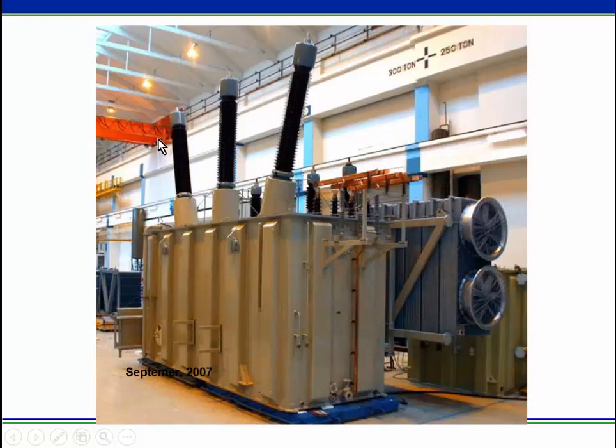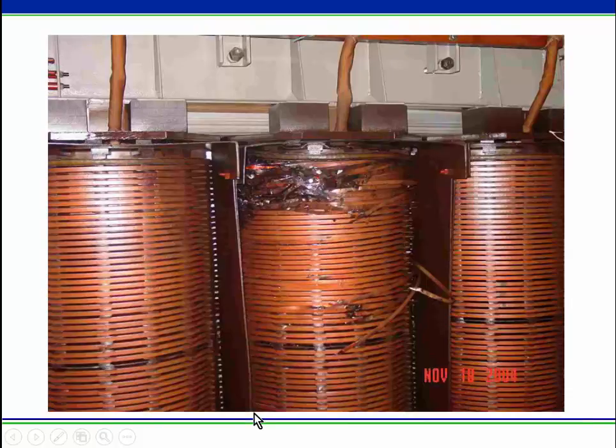Here's a nice picture of the bushings. That's probably one of the most common places for a substation transformer to have trouble. They're hanging out there. They have a lot of electrical stress on them, and they have a fair amount of physical stress too because they're swinging in the wind and they've got some terminations on them.